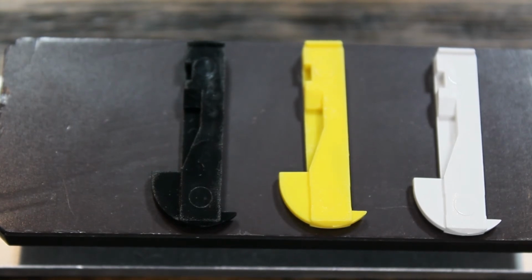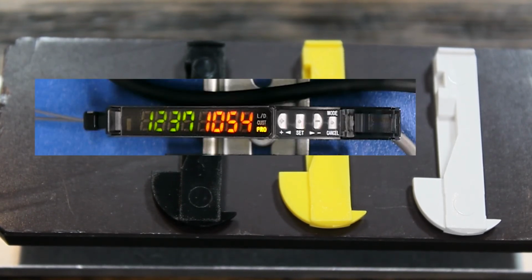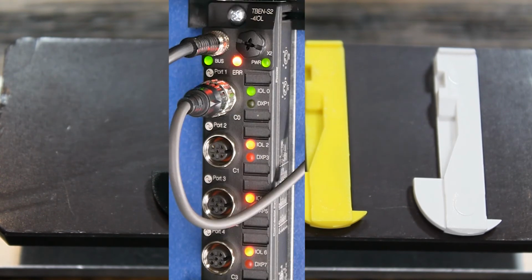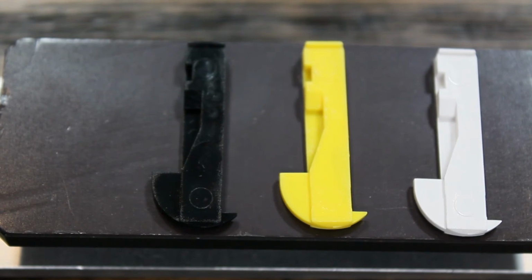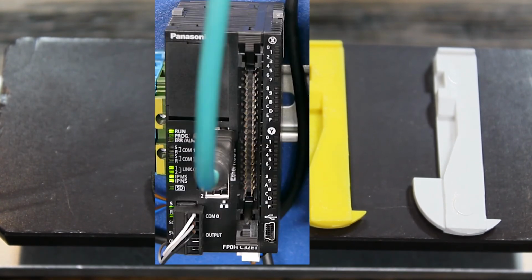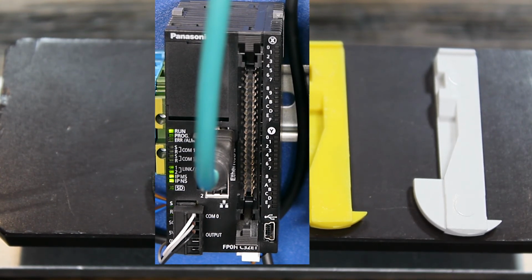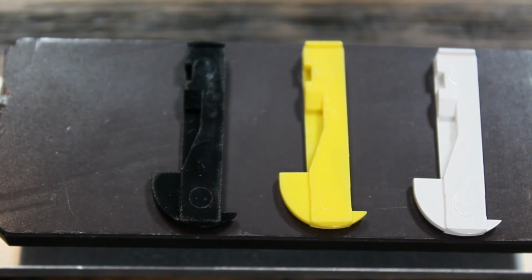So one way to solve this application is to use a Panasonic IO-Link fiber optic amplifier, the FX551L. Now we're going to take that FX551L IO-Link sensor into a Turck IO-Link master that communicates via Ethernet IP. One very cost-effective Ethernet IP PLC that we can use is the Panasonic FP0H. The FP0H has an Ethernet IP port and it'll allow cyclical communications between the sensor and the PLC. So let's go ahead and set this up and I'll show how this works.